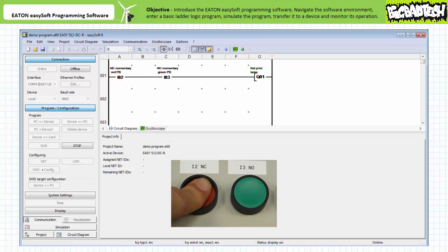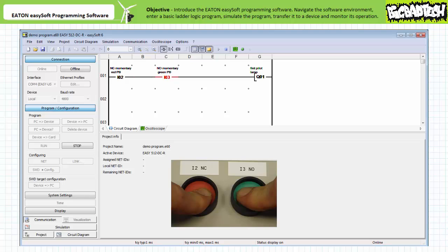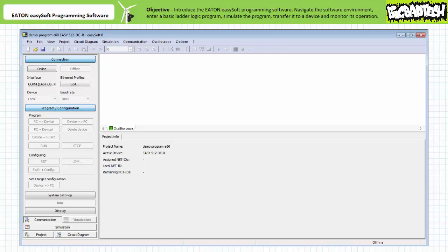When only the field input device attached to input I2, the normally closed red push button, is actuated, the remote monitoring utility indicates the make instruction examining I2 does not permit logical continuity onto the output and output coil Q1 is de-energized. When only the field input device attached to input I3, the normally open green push button, is actuated, the remote monitoring utility indicates the series connection of the make instructions examining both inputs I2 and I3 permit logical continuity onto the output and output coil Q1 is energized. When both field input devices are actuated, the make instruction examining I2 does not permit logical continuity onto the output regardless of the status of I3, and output coil Q1 is de-energized. This remotely monitored PLC is behaving as anticipated to real-world field input. We can be reasonably certain this program will function as intended, and the communication link can be broken by going offline and the PLC placed in service by entering run mode.